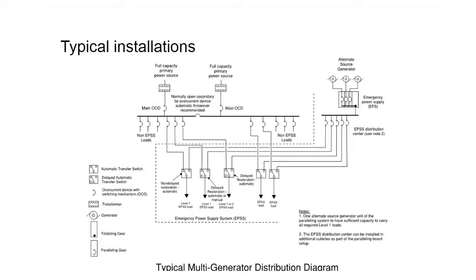If you have a typical or a multiple generator distribution system, same components generally as the one we just showed, the difference being really on the generator side. And oftentimes you'll see this because of scale or capacity that's required to serve the load. Multiple generators are paralleled together, and in this case, obviously you need to implement a load shed or load control system.